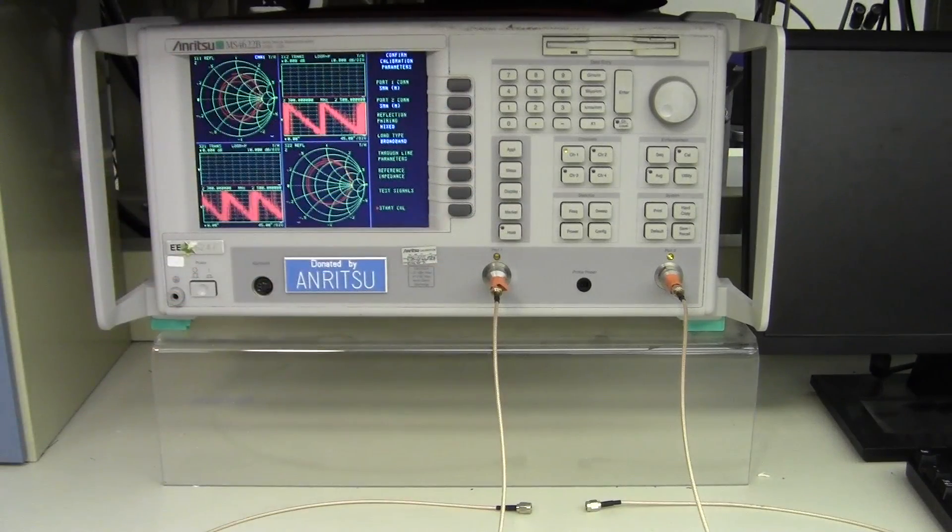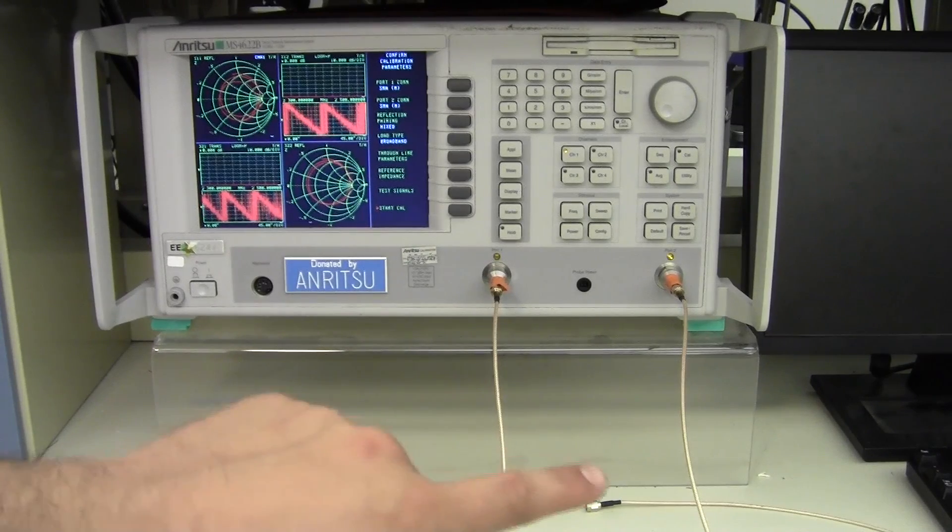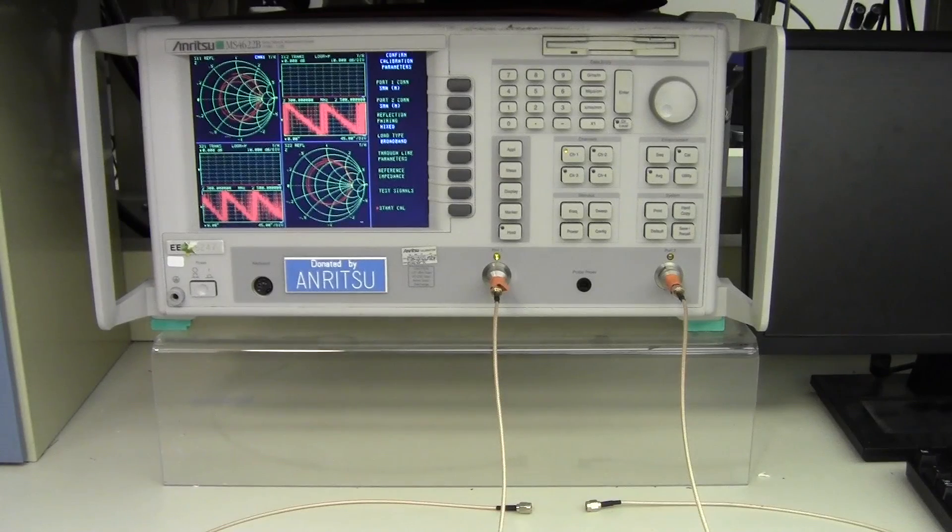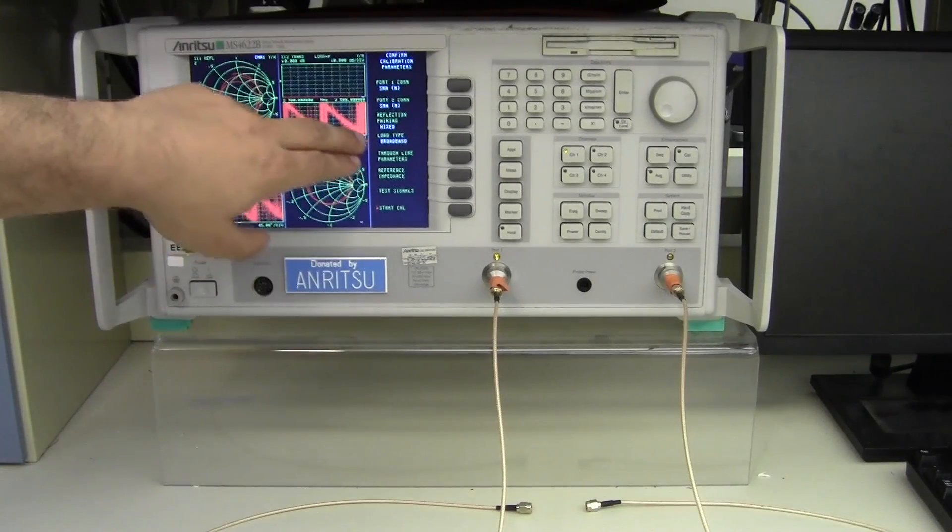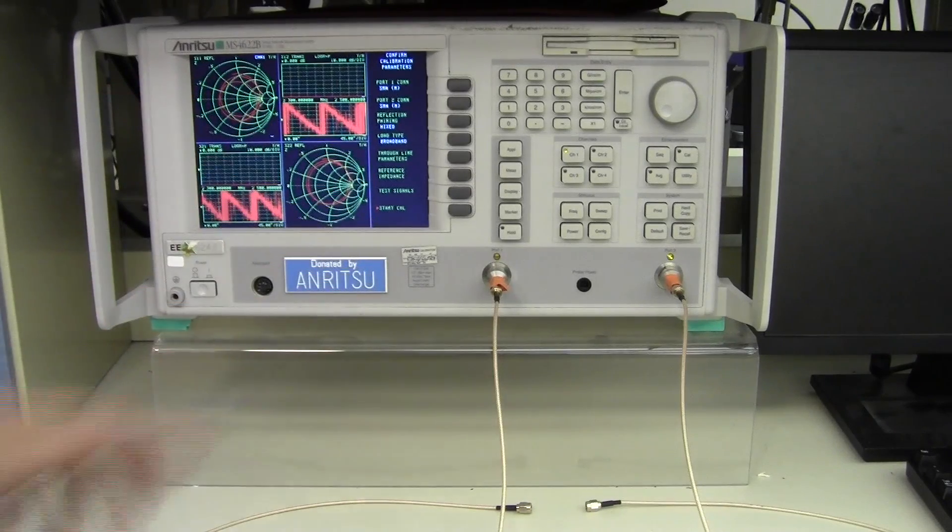Reflection pairing refers to the calibration step where we're going to be using the open and short, and it asks if we would like to use either a mixed pair or a matched pair. Our calibration kits only have one of each, so we need to have a mixed so that we can put the short on one port and the open on the other port and then switch them. Load type is broadband.